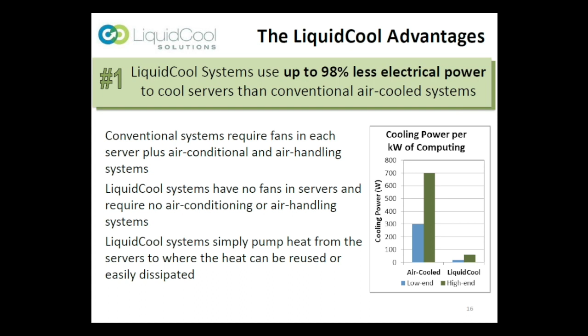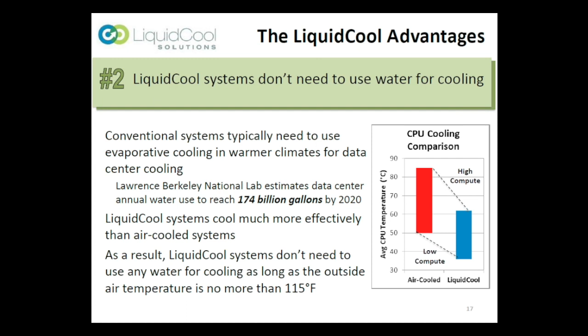A second advantage is that our systems don't need to use water for cooling in almost any climate. Now, didn't I say that the conventional servers are air-cooled? Well, in certain climates, quite a bit of water is used because an approach called evaporative cooling is needed, particularly in warmer climates. And I picked up an estimate by the Lawrence Berkeley lab that projected that water use for cooling data centers would reach 174 billion gallons in just 3 years. So that's a lot of water consumption. Now, the reason that we don't need to use water for cooling is that cooling with our liquid and our directed flow approach keeps the server components between, say, 30 degrees Fahrenheit and 50 degrees Fahrenheit cooler. So we don't have to resort to an evaporative approach as long as the outside air temperature is no more than 115 degrees, which is almost any climate in the world.